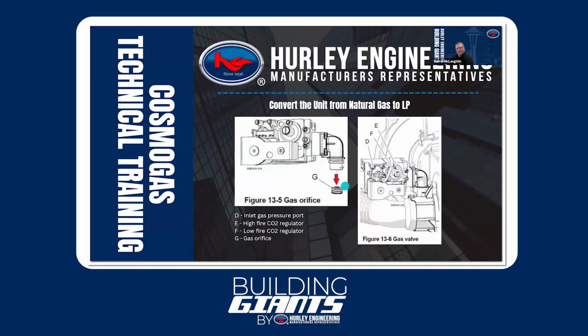Next here, you can see this is the location of our gas orifice. It comes standard on every boiler, but we do get the propane orifice as well. So if you ever have to pull that out and put propane in, this is where it goes. You can see where it's going into the suction side of the blower, and then you'd have to adjust the regulators accordingly.